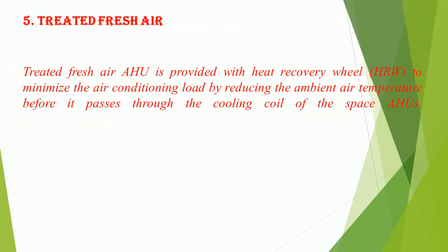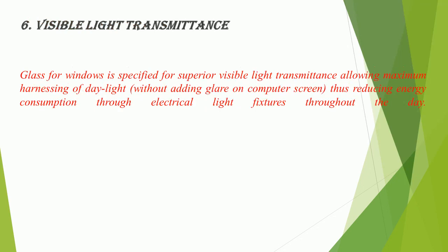Feature 5: Treated Fresh Air — the Treated Fresh Air AHU is provided with a heat recovery wheel (HRW) to minimize the air conditioning load by reducing the ambient air temperature before it passes through the cooling coil of the space AHUs.